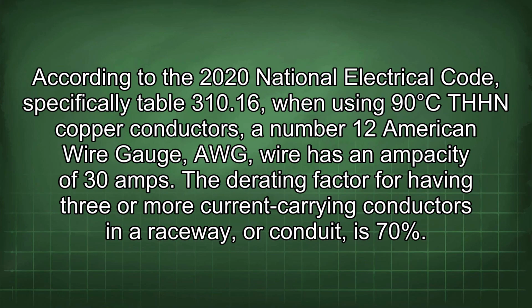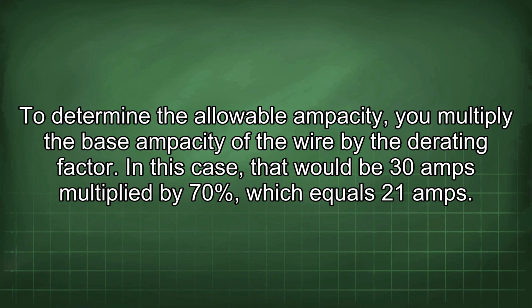According to the 2020 National Electrical Code, specifically Table 310.16, when using 90 degrees C THHN copper conductors, a number 12 American wire gauge (AWG) wire has an ampacity of 30 amps. The derating factor for having 3 or more current-carrying conductors in a raceway, or conduit, is 70%. To determine the allowable ampacity, you multiply the base ampacity of the wire by the derating factor. In this case, that would be 30 amps multiplied by 70%, which equals 21 amps.